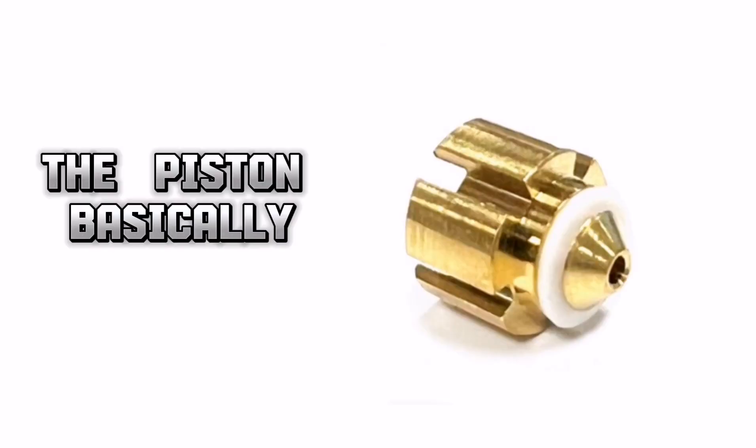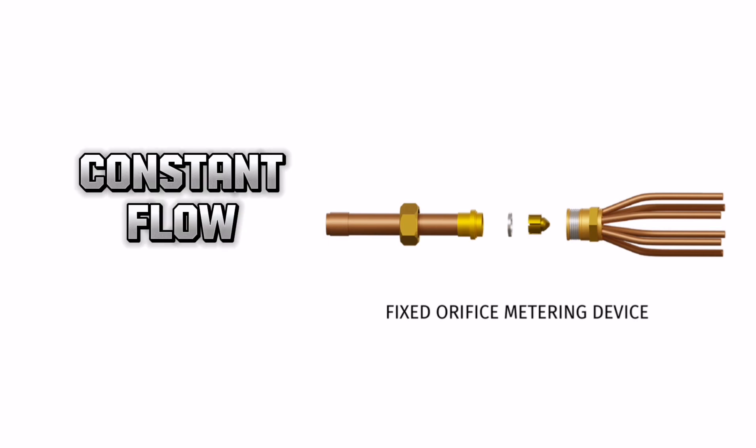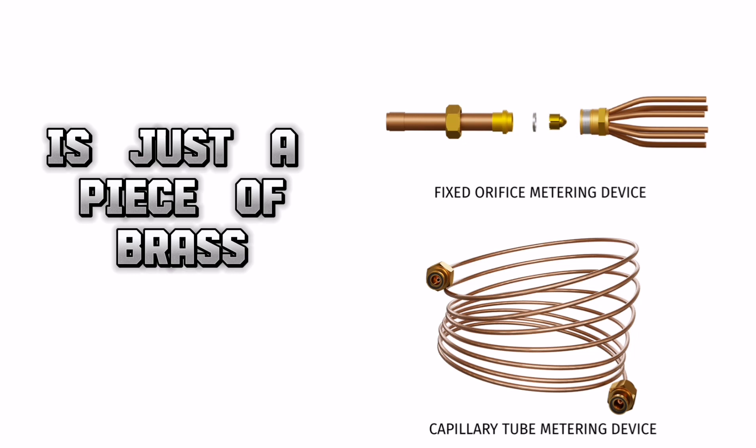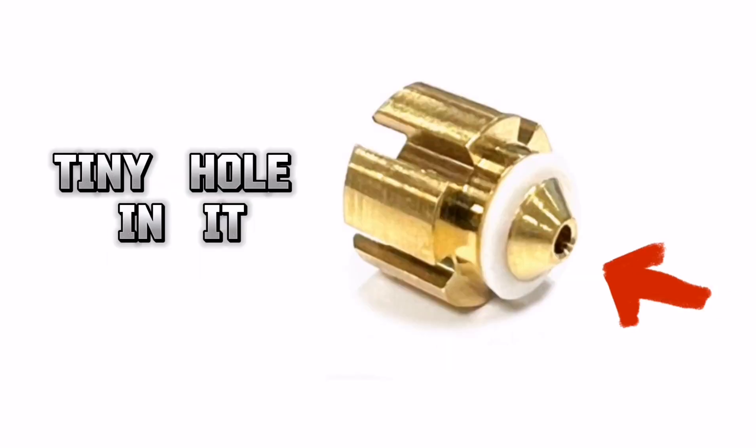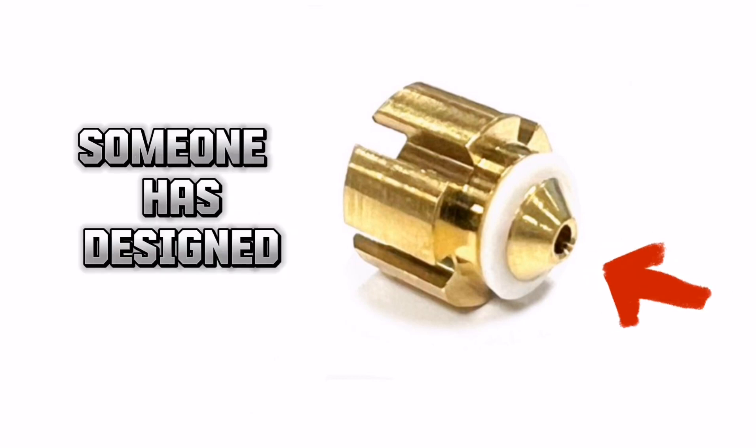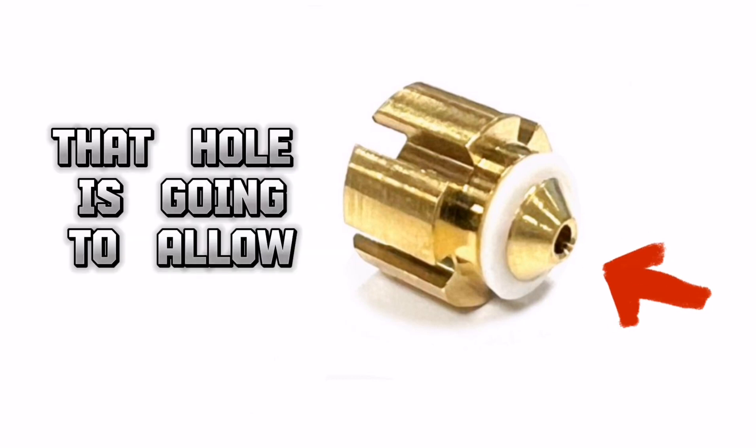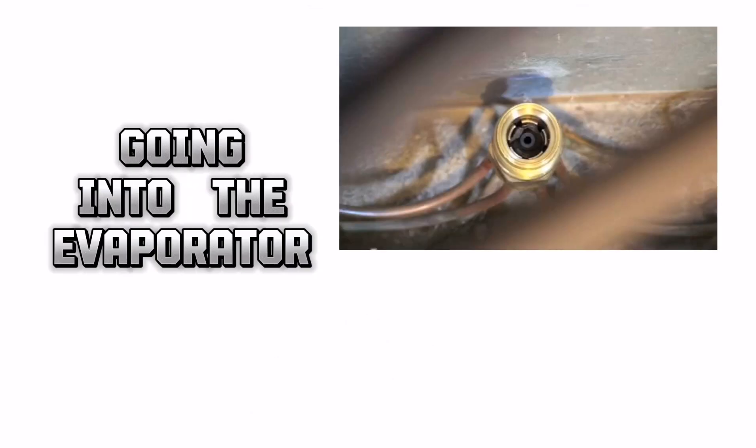The other one is the piston. The piston, basically, it's going to be maintaining constant flow, just like the capillary tube. And all it is, is just a piece of brass that they have machined, and it has a little tiny hole in it. Now, that hole, some engineer, someone has designed it so that that hole, it's going to allow that specific flow going into the evaporator.